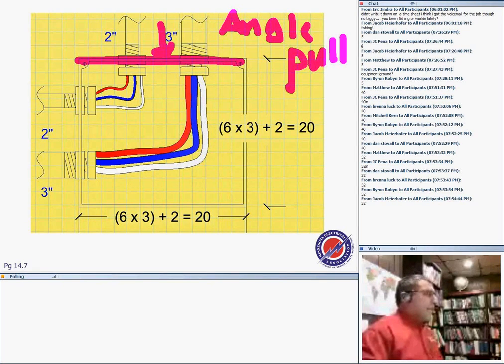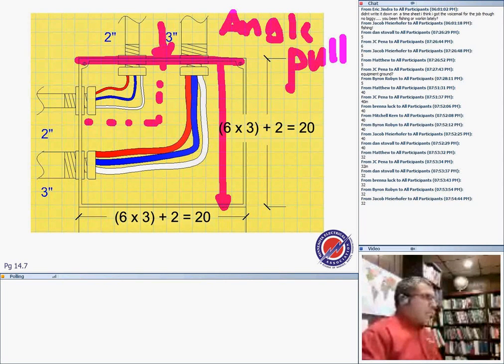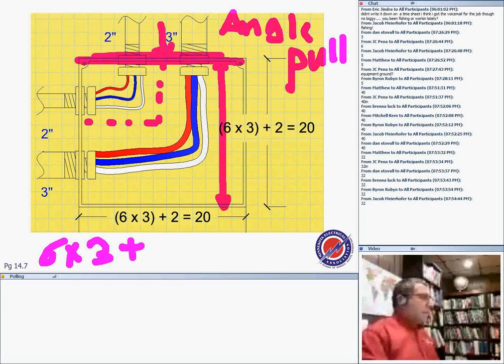So that's coming from this wall, and where are they going? Going to the left. Coming from the top, going to the left. Looking at it from the top, that will give me this dimension, the one opposite to where the conduits enter. The code says it's 6 times the largest conduit on that wall, which is 3, plus the other conduits sharing the same wall, which is 2. That would be 20.